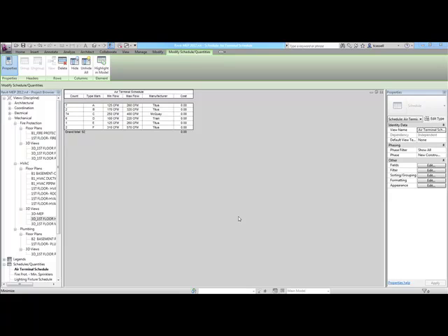Because Revit's database driven as well, all of that information stored on multiple floors gets consolidated in a single schedule, which I'll come back and talk more about later. But as you can see, this is a grand total count of all diffusers that are currently in this project. And this number will grow as we add more diffusers to multiple floors. Again, no need to XREF multiple files together in order to get full accurate counts as you would in AutoCAD MEP.